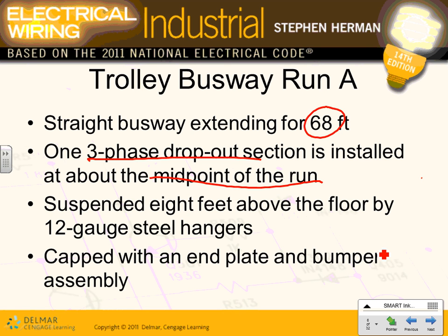So the way they're feeding it, looks like they're feeding it right in here. I don't know if you guys can see that section here. Right in this, where they brought the power, right in the middle of it. You can bring the power in the middle of it, Jeff, or on the sides. So they're bringing that one in the middle. This is important for you guys when you put your busways.